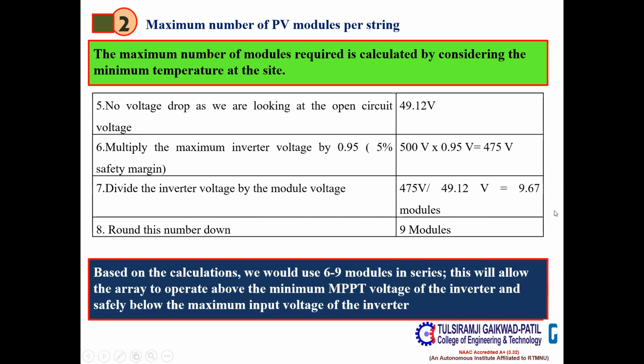Again, as we are considering the maximum part, no voltage drop is considered here, because we need to calculate the maximum number of modules. So we will take it as it is, that is 49.12 volt. Now, as we are moving to the maximum part, we need the higher limit of the inverter voltage, that is 500 volt. But we cannot reach exactly the higher limit; we have to keep some safety margin. I have taken the safety margin as 5%, and it would be 475 volt.